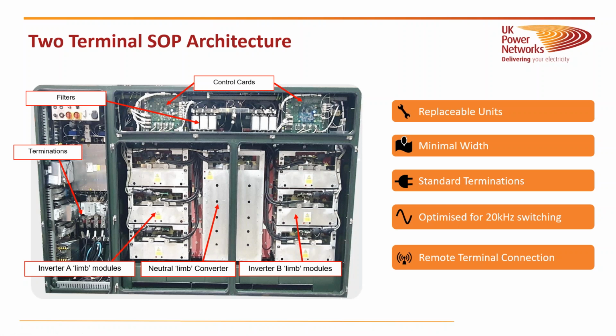The other thing we've had to design it with is, it's got to be installed on a pavement, as Luca said. So it's got minimal width. It's about 0.5 meter wide, which allows it to be installed on pavements. We've also designed it to be easy for our operations guys to install. There are the terminals down here on the bottom left, and these are the standard LV terminations that we use for various other LV equipment, such as cutouts. So that follows our jointing standards.